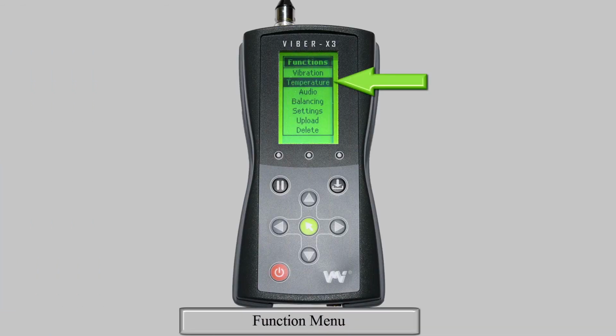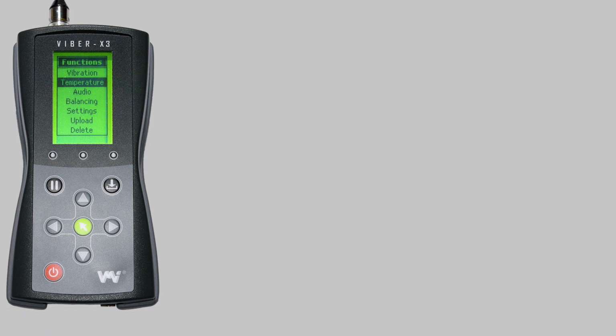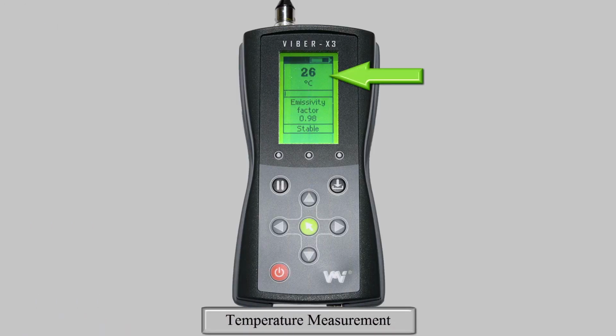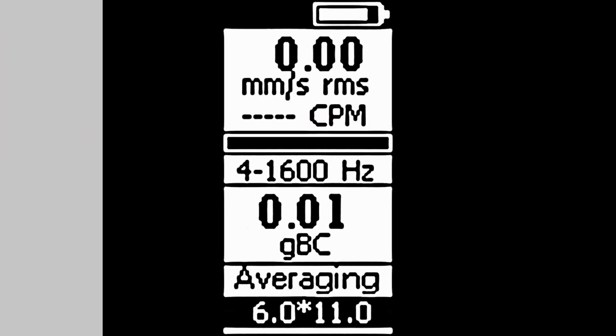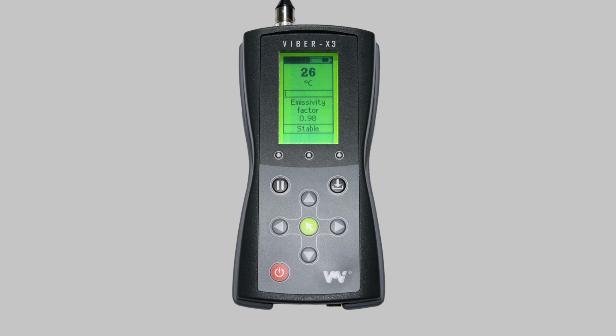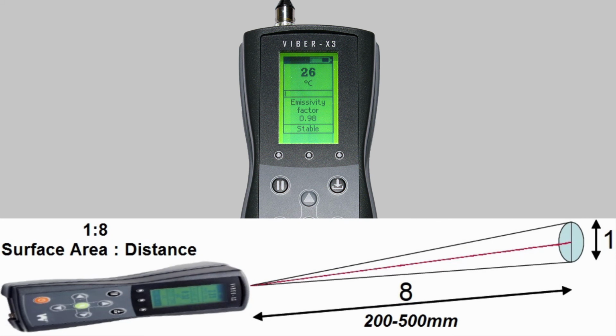To take a temperature measurement, select Temperature in the Functions menu. The digital display will show the measured temperature, stability bar, the selected emissivity factor, and a measurement status, which will be either averaging, stable, overflow, or 3 stars. These statuses represent the same as for a vibration measurement. When taking a temperature measurement, direct the IR transducer towards the measurement point and keep a distance of approximately 200 to 500 millimeters, and ensure the stability bar and measurement statuses are both stable before recording the reading.